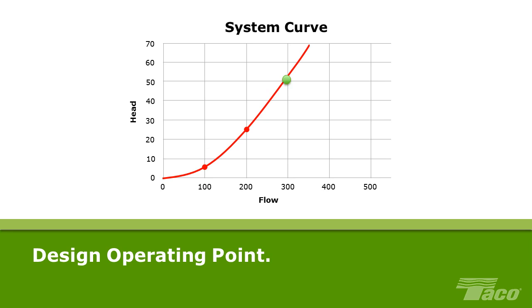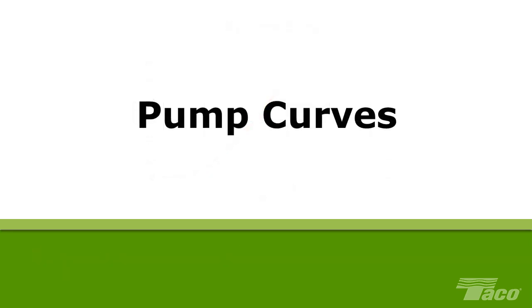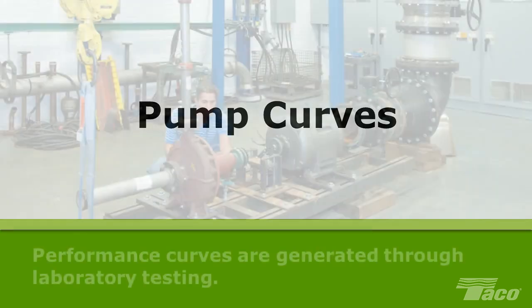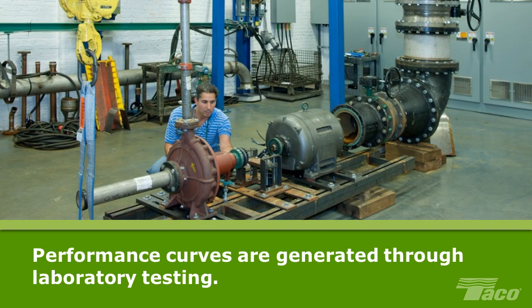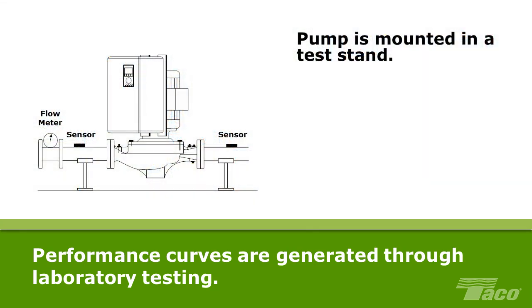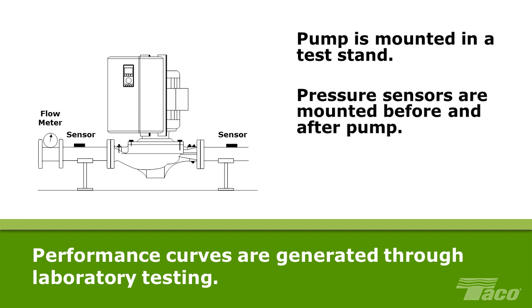As we will see later in this video, system curves change in characteristic ways when the system operates below its design point, in other words, at less than the maximum flow rate. Pump curves. Pump manufacturers generate pump performance curves by laboratory testing rather than by using a formula. The pump is mounted in a test stand. Pressure sensors are mounted before and after the pump.